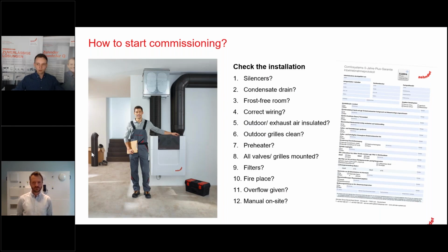So with that documentation, you then go on site, and before we start with the actual process of commissioning, we need to check the whole system, whether everything is installed correctly. And therefore, we have a checklist which should be taken to every commissioning. So at the beginning, you need to check, for example, if the silencers are in a correct position, and is the condensation drain connected, if it is necessary at all. You know, for the enthalpy exchanger, you don't need a condensation drain, for example.